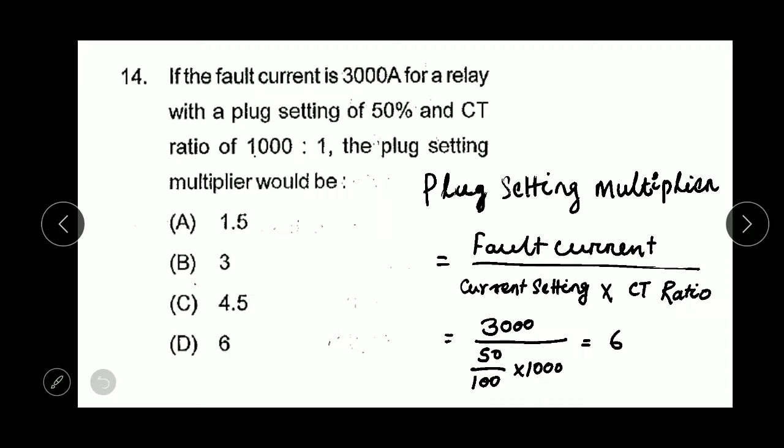Question number 14: If the fault current is 3000 ampere for a relay with a plug setting of 50% and CT ratio of 1000 to 1, the plug setting multiplier would be? The formula is fault current by current setting times CT ratio. We calculate 3000 divided by 50% times 1000, which equals 6. Option D is correct.